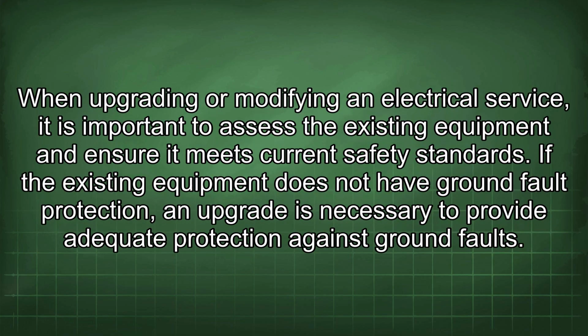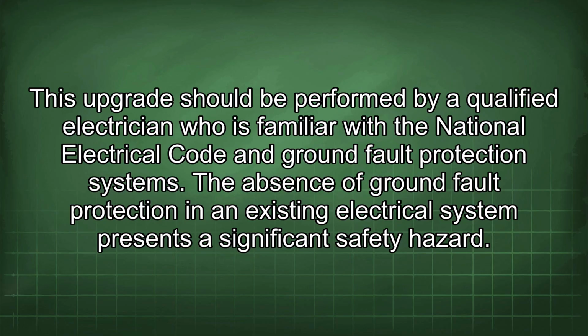When upgrading or modifying an electrical service, it is important to assess the existing equipment and ensure it meets current safety standards. If the existing equipment does not have ground fault protection, an upgrade is necessary to provide adequate protection against ground faults. This upgrade should be performed by a qualified electrician who is familiar with the National Electrical Code and ground fault protection systems.